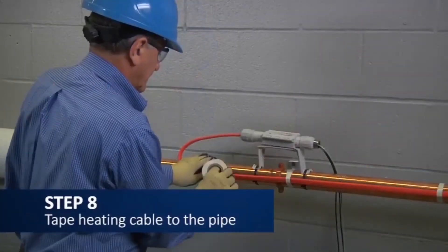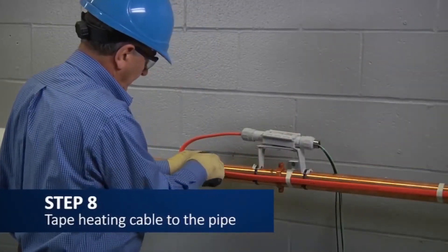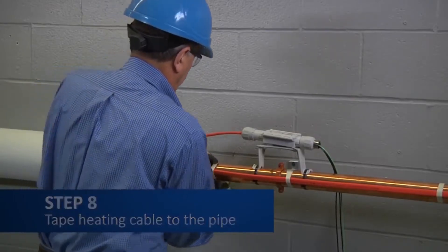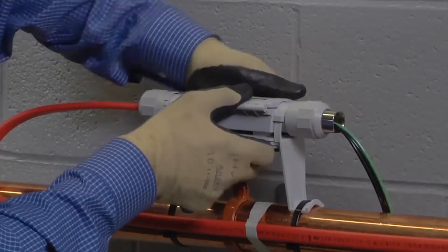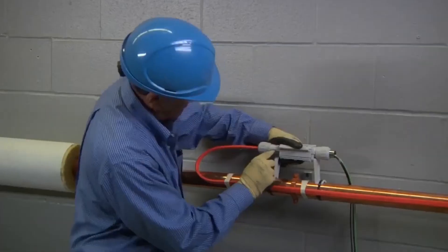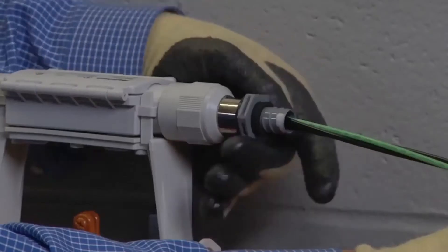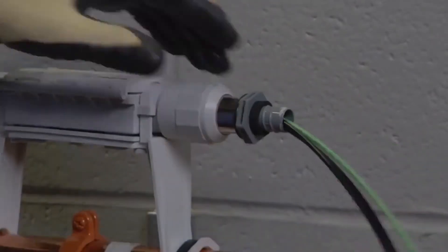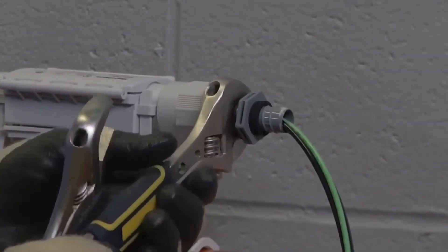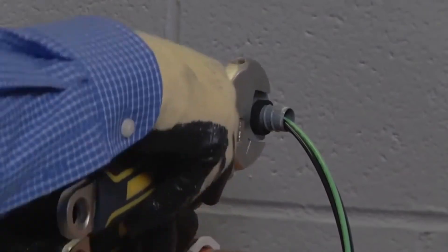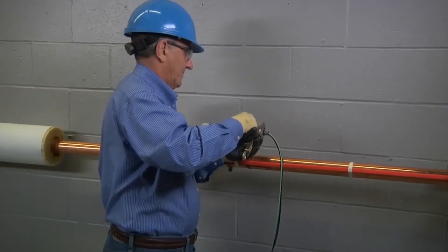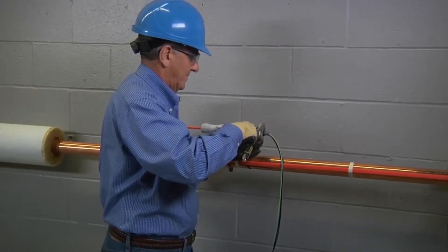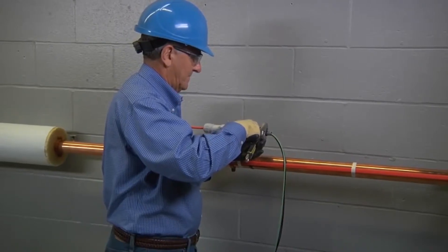Now, tape the last part of the heating cable flush to the pipe to complete the service loop, and snap the RayClick PC fitting into the pipe bracket to secure it in place. Using the two wrenches, attach a user-supplied ½ inch threaded conduit fitting to the end of the RayClick PC fitting body. Avoid using excessive pressure and breaking the female conduit fitting on the RayClick PC.